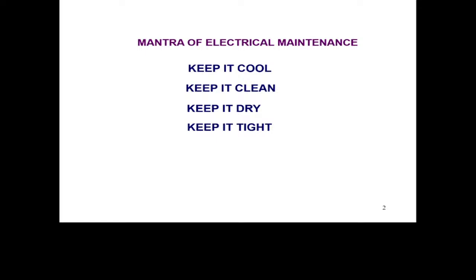That's preventive. Similarly, keep it cool—things like OTI, WTI, and cooling systems are basically about preventing aging of insulation. Keep it dry—when we talk about moisture content in oil, it should be less than 5 ppm; that's keeping it dry. Keep it tight—wherever you have bolts and nuts, if they're not tight you'll get oil leakage. Recently, Boeing suffered a door coming off because some bolts were not kept tight—simply because some people did not keep it tight.